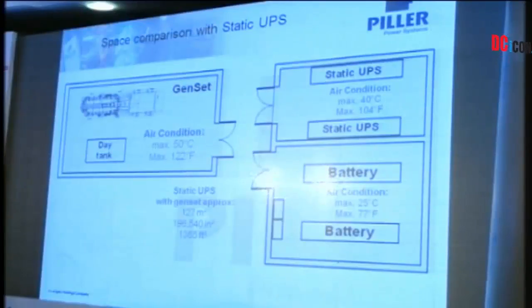Okay. I talked about space. Reliability, efficiency we've seen. I also talked about space. So here is a comparison of how a static UPS configuration with genset would look compared to a diesel rotary UPS. So here's the static UPS. We don't cool the static UPS. Static UPS are capable of running at 40-degree ambient temperature. Batteries are at an ambient temperature of 25 degrees Celsius.